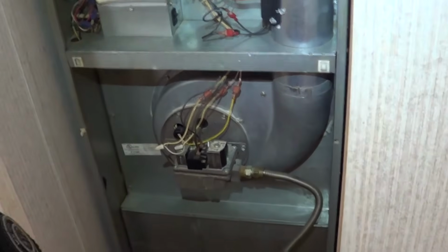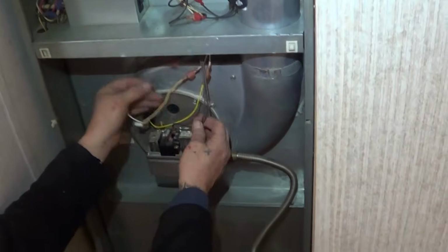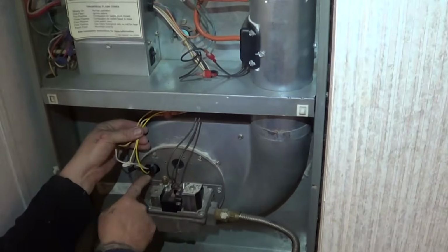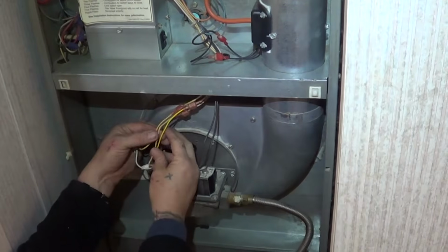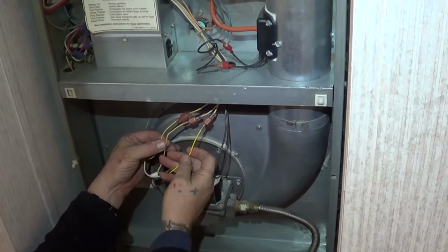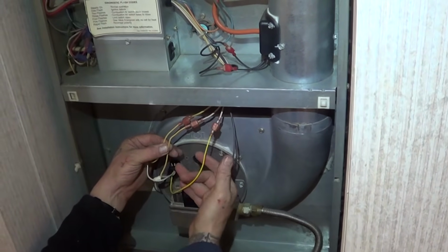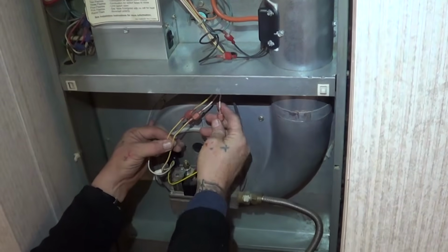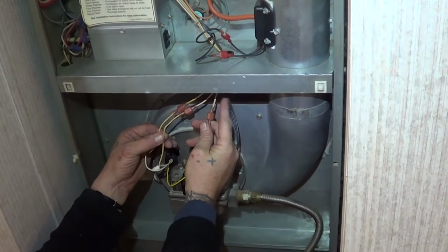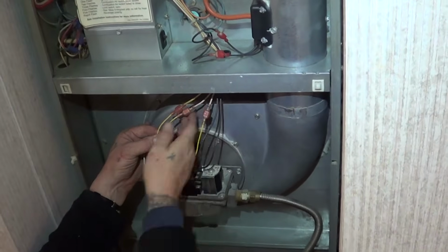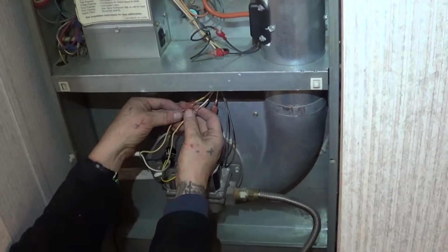This one's a bit different than the last one we looked at. There are three wires here going inside: two for the igniter and one for the flame sensor. The yellow wire is the flame sensor, and we'll make sure that gets hooked back up exactly to the flame sensor wire, so you might want to mark these. The igniter wires don't really matter which way they get hooked up.